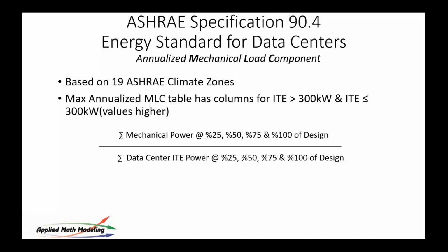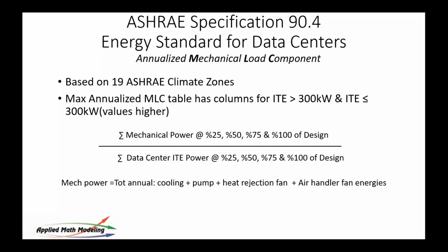So this was an attempt to try to put some better fundamentals in place and better metrics in place. And here we're talking about the mechanical power being the sum of everything. So it's really a systems level coefficient of performance kind of ratio. It includes cooling pumps, heat rejection fans, air handlers, etc. So we think this makes a lot of sense. And of course, now there's criteria that you can meet. And it ends up, as I mentioned, being essentially the inverse of COP for the entire data center operation, which is a good thing.